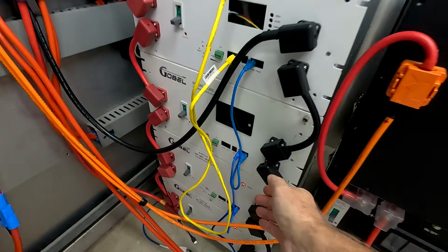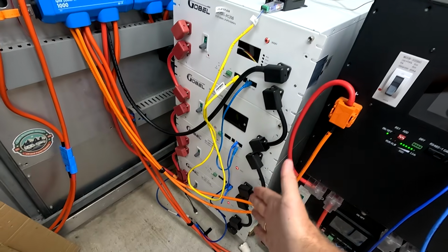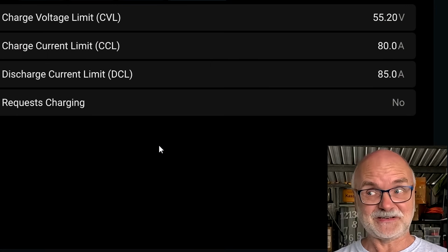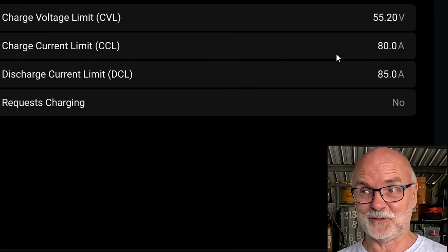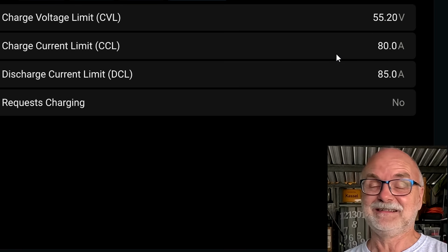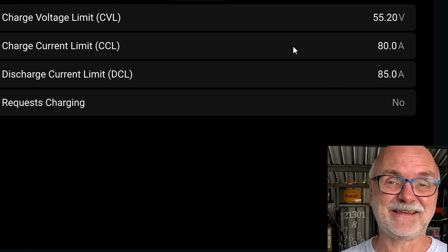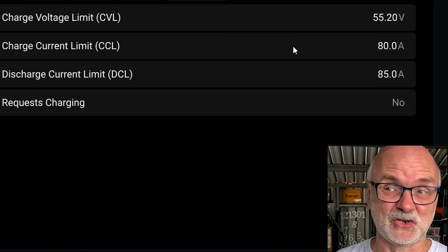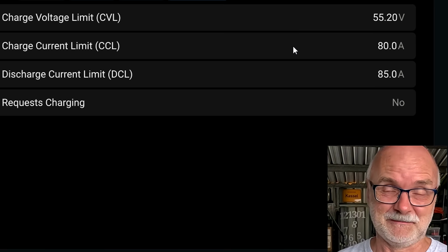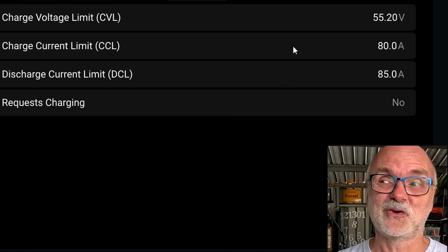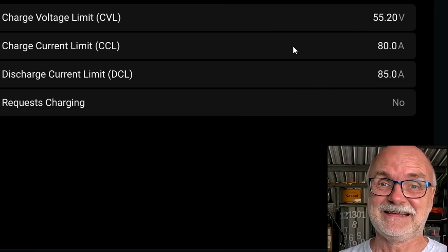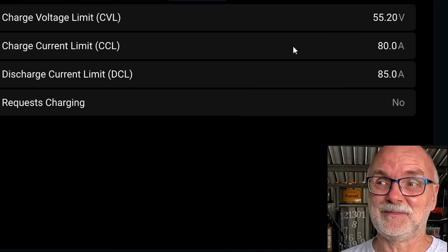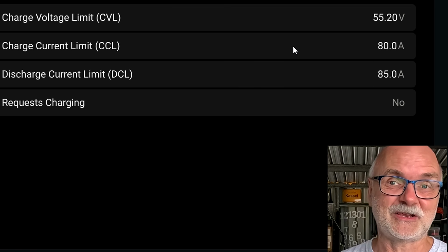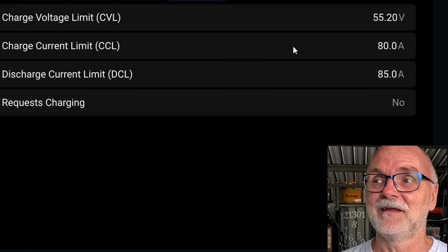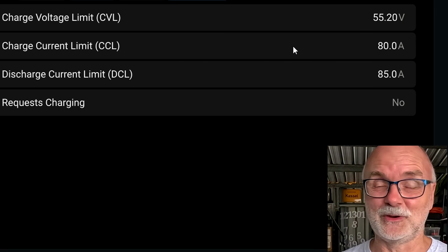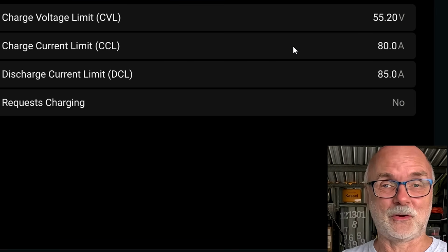And this is even worse if we unplug, for example, 3 of the 4 batteries. So the master is now alone and it reports 80 amps to your inverter, of course, because it sees there's only one BMS connected, so everything is safe. You had a lightning strike somewhere in your neighborhood or something, there was a surge, and 3 of your BMSs are grilled. But these 3 batteries are still physically connected to your system and are still charging. They are not being monitored anymore by the BMS. The BMS is not reacting to over voltage protection, over temperature, over current, whatever you name it. The master doesn't know about it and doesn't send you a notification or warning anymore. Everything is clear. You've got only one BMS connected.